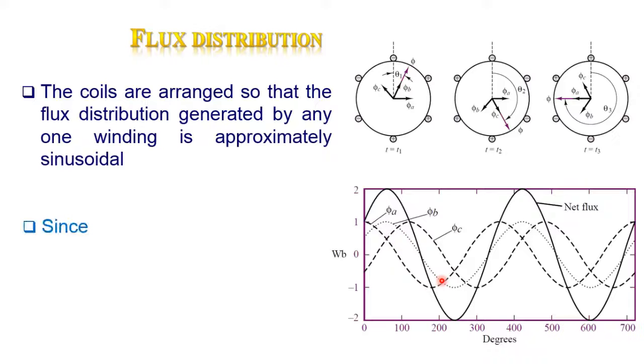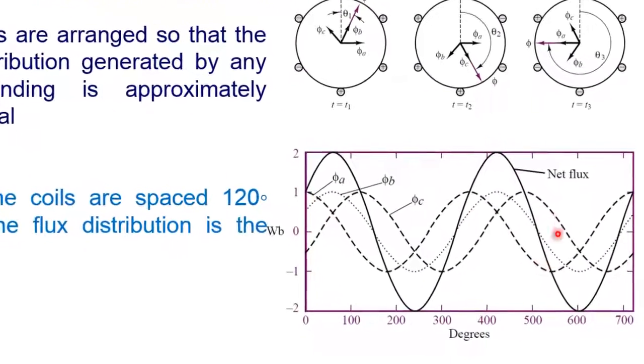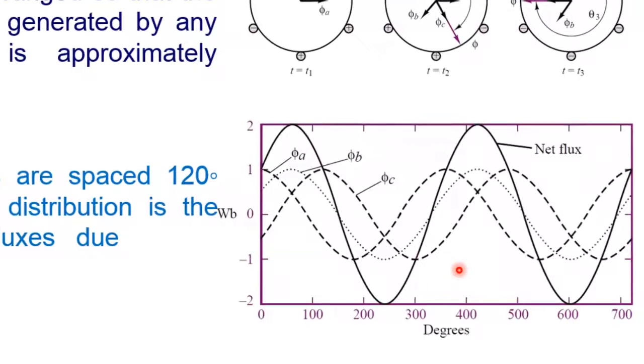Since the coils are spaced 120 degrees apart, the flux distribution is the sum of the fluxes of all three windings flux. Therefore the net flux in three-phase motor is constantly rotating vector with constant amplitude.